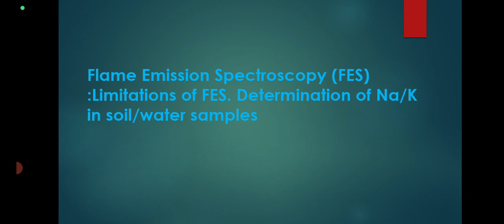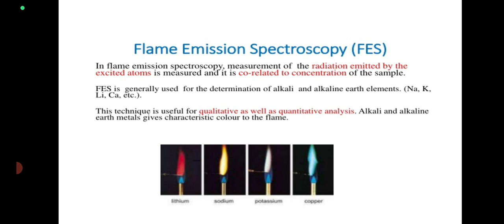Flame emission spectroscopy. In flame emission spectroscopy, the radiation emitted by the excited atoms is measured and correlated to the concentration of the sample. FES is generally used for the determination of alkali and alkaline earth elements. This technique is useful for qualitative as well as quantitative analysis. Alkali and alkaline earth metals give a characteristic color to the flame.